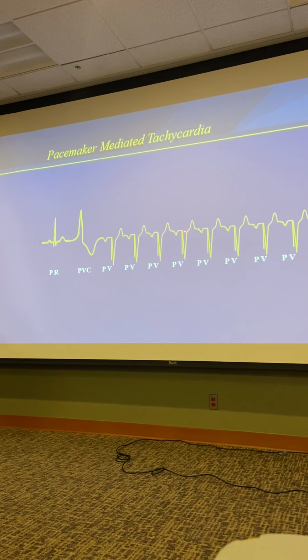The trick for stopping this, of course, is to just prevent one beat from traveling backwards through the atrium, or prevent the pacemaker from tracking that. So you can apply a magnet. The magnet makes it asynchronous. It's not going to care what the heart is doing. If it's programmed at 60 beats per minute or at 90 beats per minute, you put the magnet on, count to 3, take it off, and that circuit won't exist anymore.